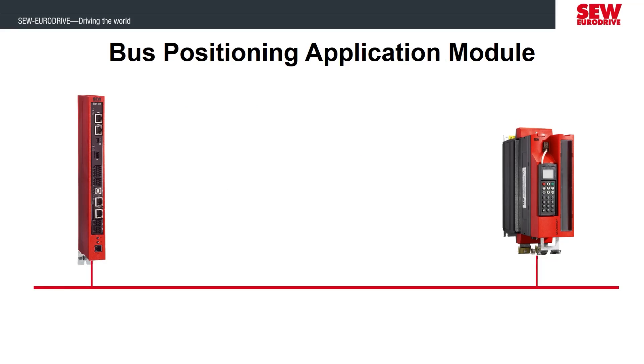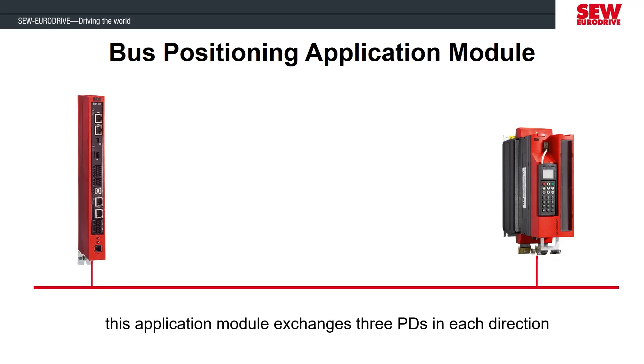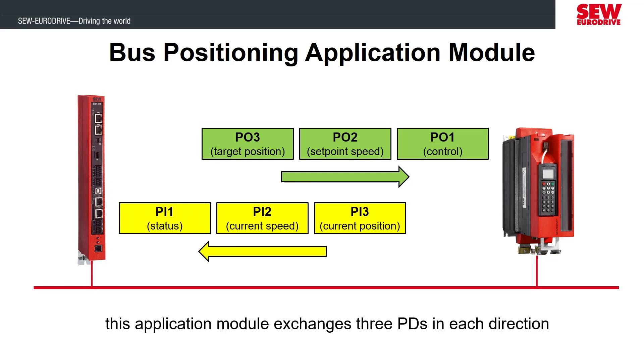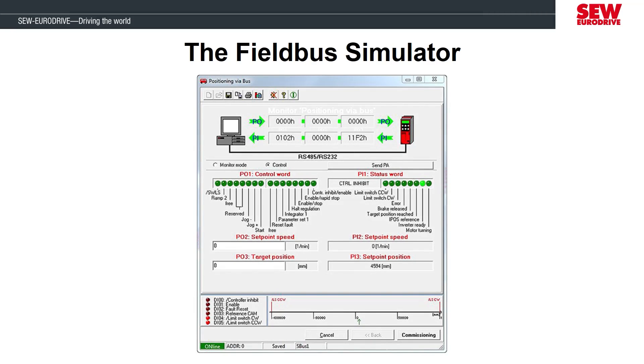Now that we've shown examples of process data words, let's get specific about the application module we'll be demonstrating: the bus positioning application module, configured to exchange three process data words in and out between the upper level device and the Movi Drive. Process output 1 is the control word, process output 2 is the set point speed, and process output 3 is the target position. The Movi Drive sends status information back upstream: process input 1 is the status word, process input 2 is the current speed, and process input 3 is the current position.